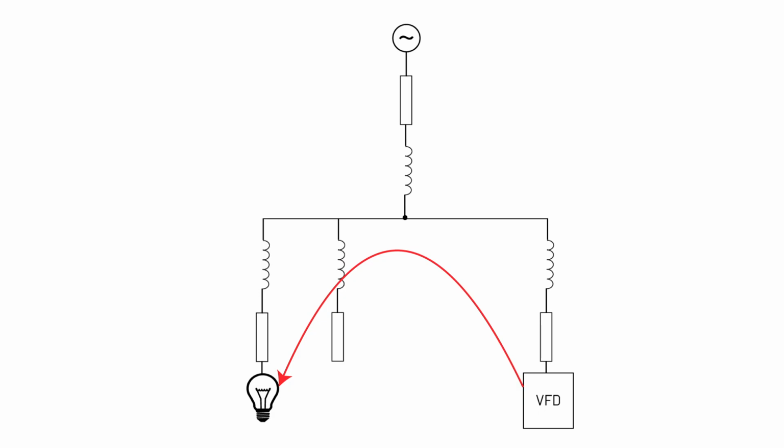So it means, in total, the voltage we get is the sum of all the impedances and all the loads together, and they are all contributing to higher harmonics. And this basic model on how current is spreading, we now made a last picture of that, where we see that harmonics can actually go from one part of the facility to another part. It applies for everything in the grid. So it applies if you have a small building, you have a lot of power supplies for your computers, and you actually get a distorted current to the light bulbs in the restroom. It applies for a large industry, but it also applies between different buildings, and it applies on entire parts of the electrical grid. So that was a very quick explanation on how harmonics are spreading.